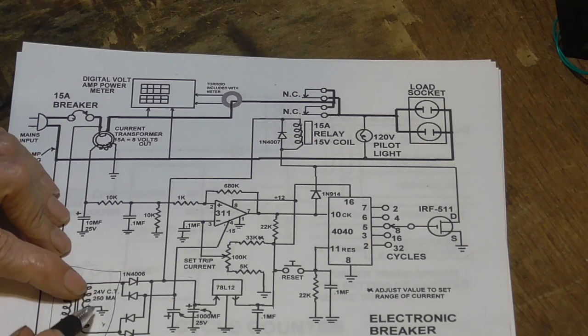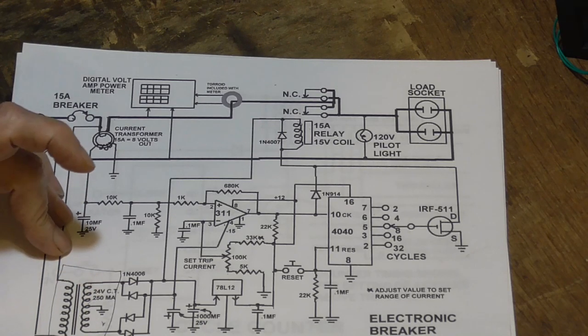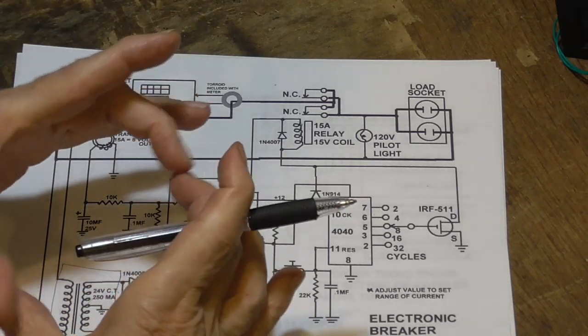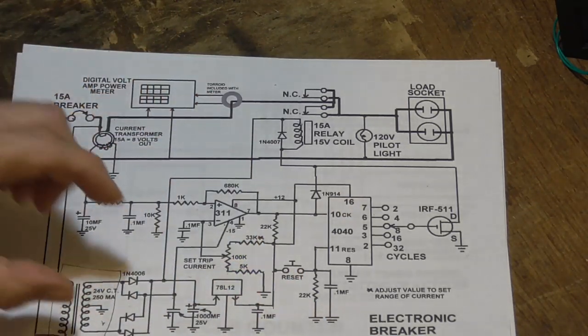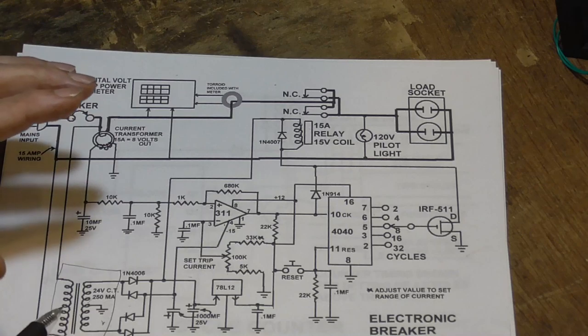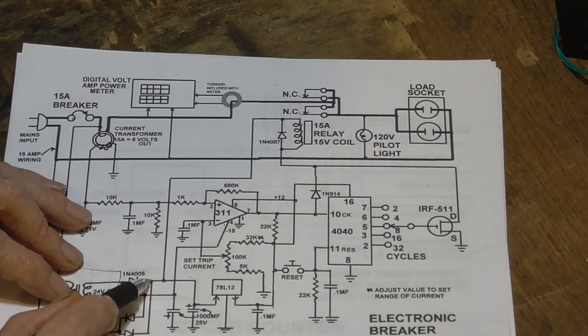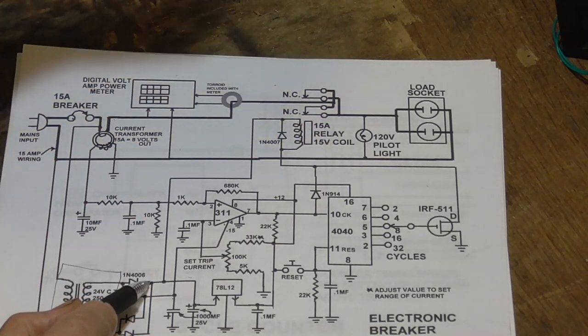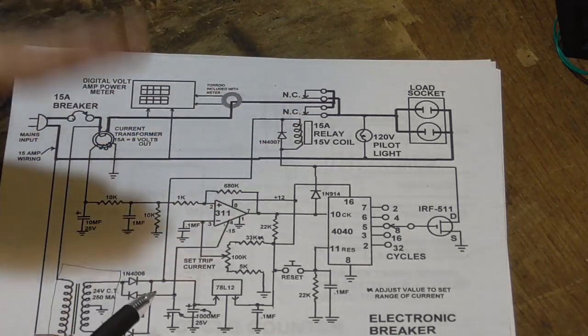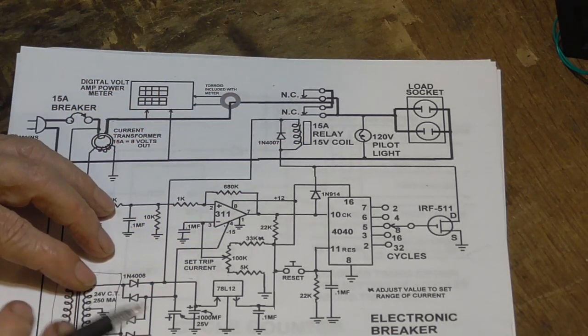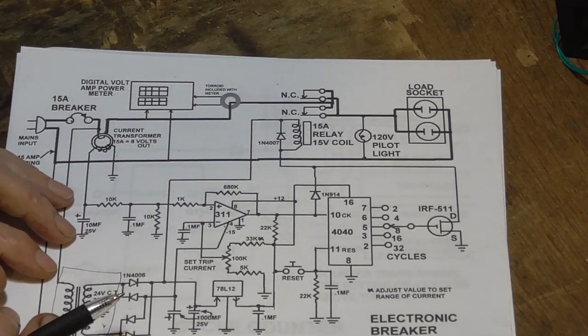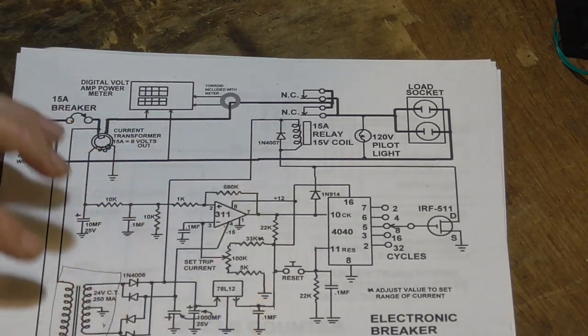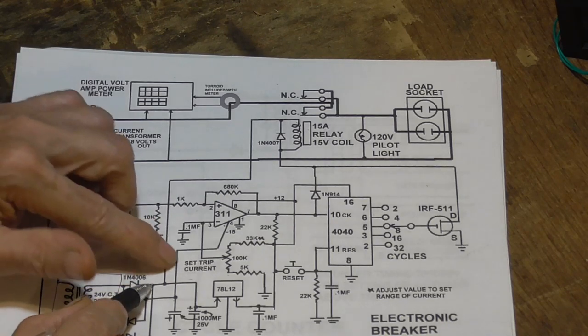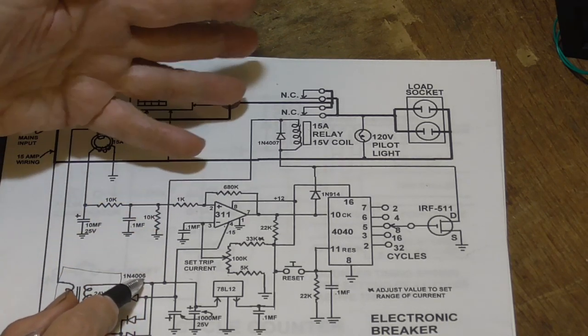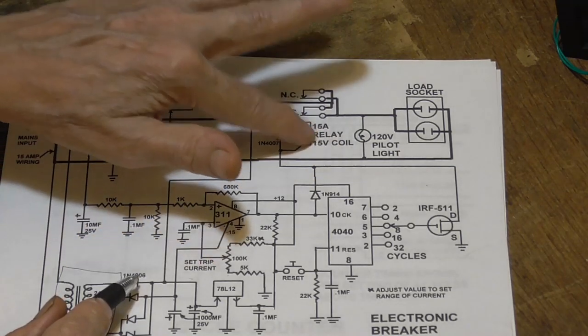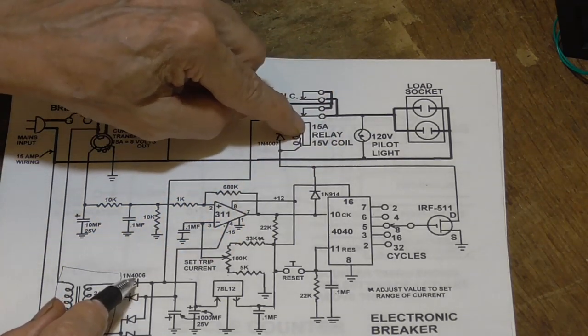Ideally, you want a 24-volt center tapped transformer. They come in all different sizes, depending on what size wall wart you use. If you get a little bitty wall wart, it may only have 100 milliamp capability, so this will load down. If you have a relay that pulls 50 or 100 milliamps, it'll load it down a little bit, so you wouldn't have any trouble using a 12-volt relay. But if you got a hefty one, a little bit bigger, this thing may maintain 16 volts on it when you put the relay load on it, so that could overstress the coil in the relay.